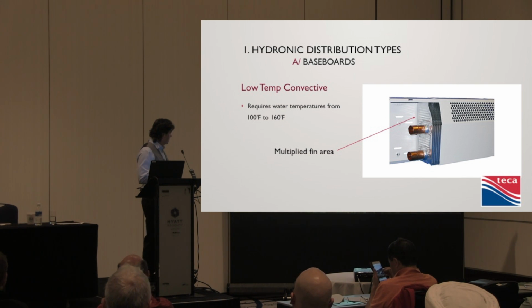Well, the other one, we just had the supply in one end and the return out the other. Here we have the supply and the return in the same baseboard, and look at all the fin tube we got in here. Lots of aluminum heat transfer surface. So we can reduce our supply water temperature because our heat emitter is more powerful. Having said that, we still have a convector.